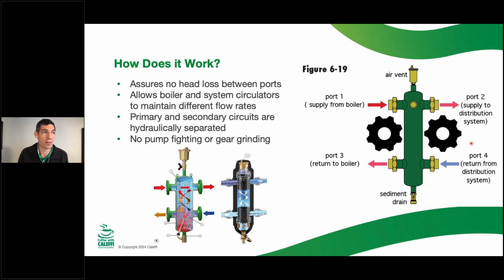That's all going to be related to the flow rates, the delta T coming back from the system. If you lose 40 degrees Fahrenheit coming back and you're mixing with something that's 5 degrees warmer on that side, this is not a temperature mixing device. You're going to need some sort of mixing strategy, if that's a thermostatic mixing valve for low temperature radiant or some sort of injection pump, whatever the case may be. This is not a mixing device.